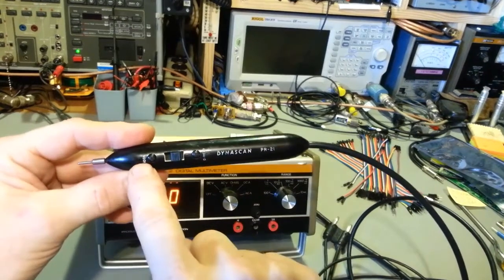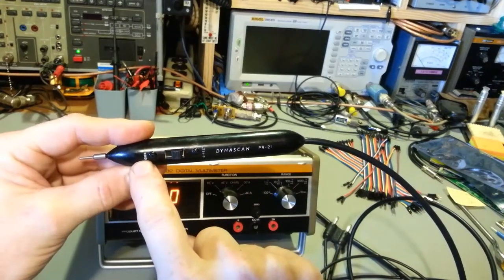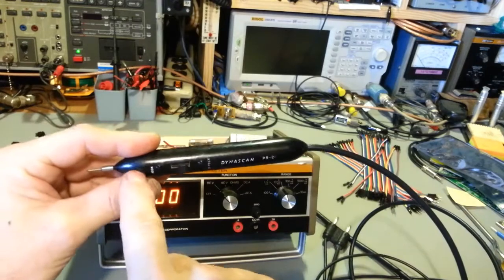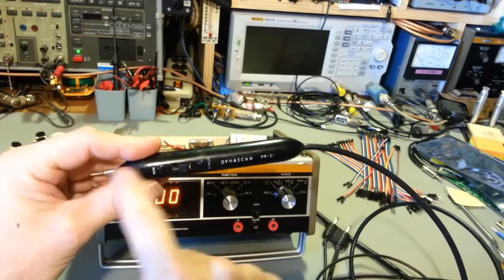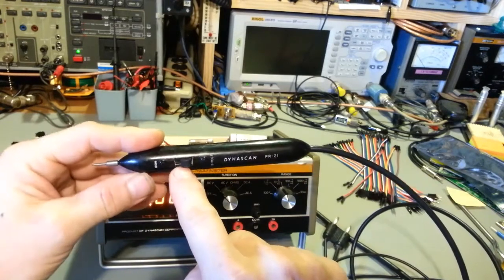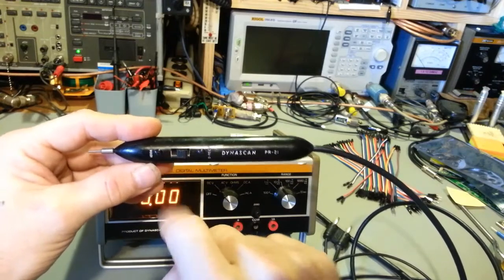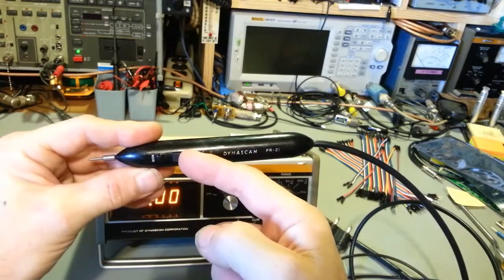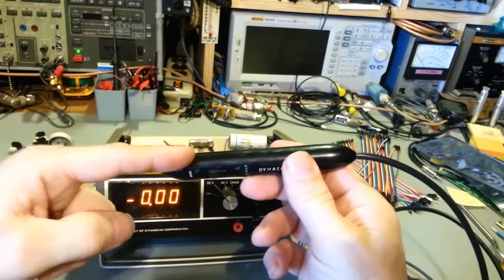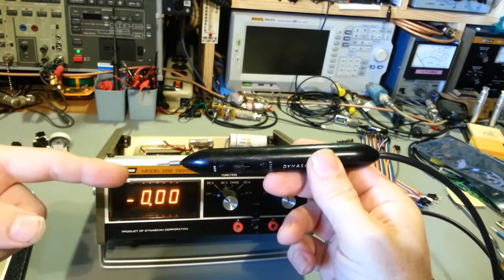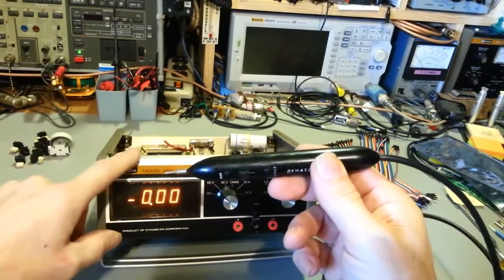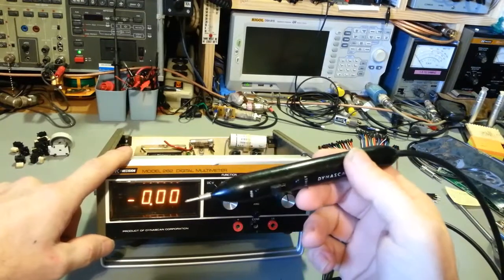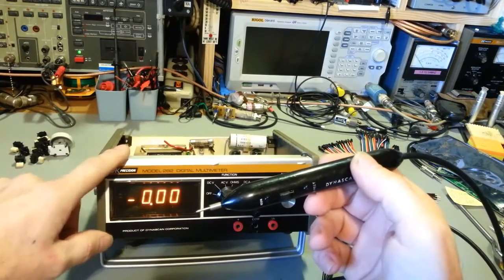This is not like a demodulator probe like you'd see on some equipment. It has a direct and a 100K position. That's 100K ohm, though actually it's very far out of spec. I measured it, and it's more like 150K. When you flick this switch into the 100K position, it adds an additional 100K of resistance in series with the meter's 10 mega ohm input divider circuit impedance.